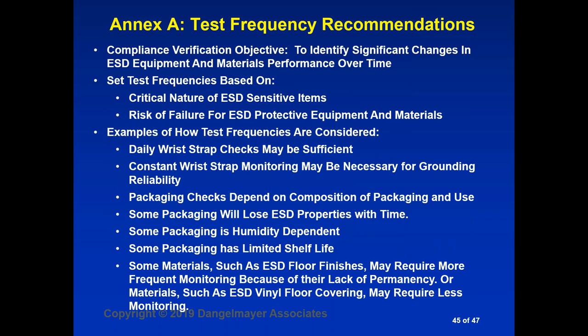So finally, after doing all of these checks and knowing about how to make the measurements, what we need to think about is how often do we make these measurements? So remember that the compliance verification objective is to identify significant changes in the ESD equipment and materials performance over time. So you'd really like to be doing your compliance verification before there's a problem with something. So basically, you're going to set your test frequencies based on how critical are the ESD sensitive items. If your items are not sensitive below 500 volts, you're probably not going to test your compliance verification that often.